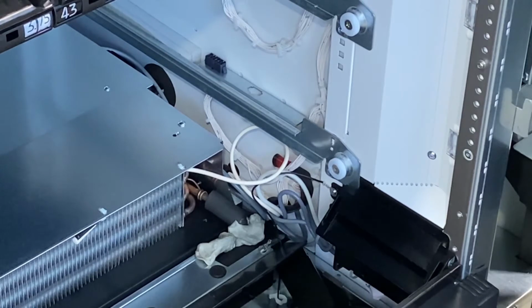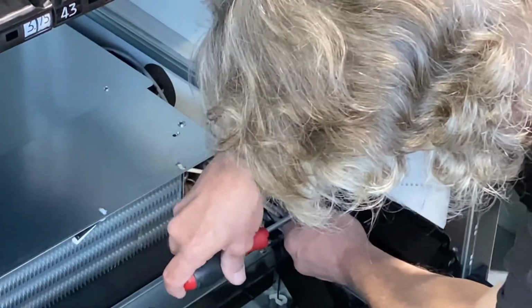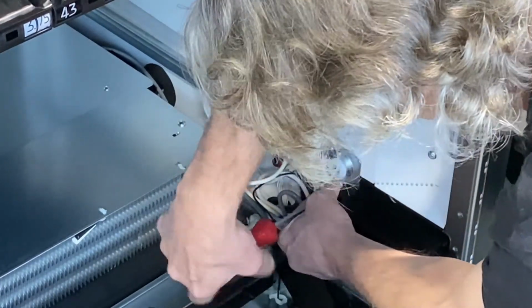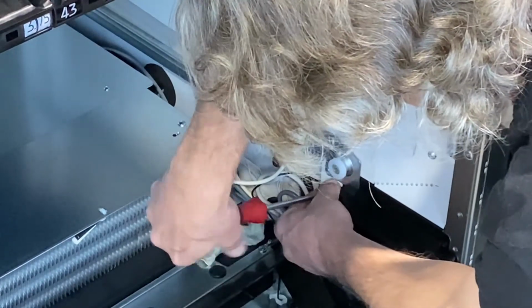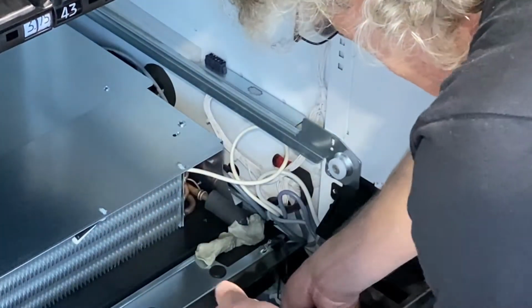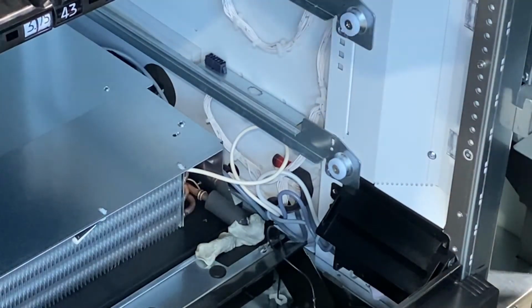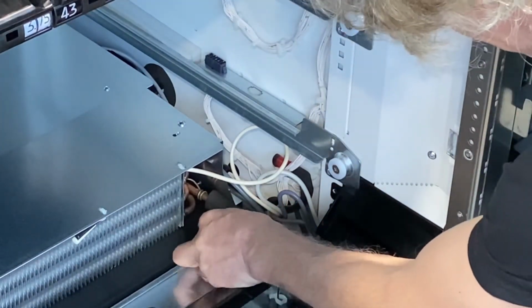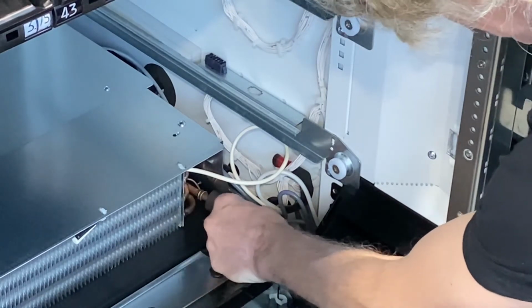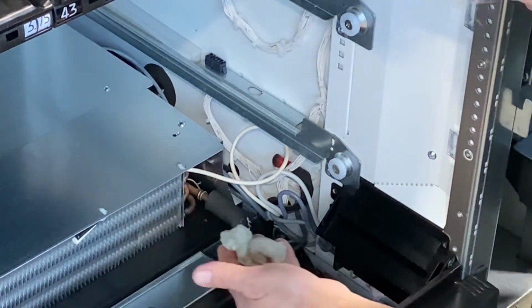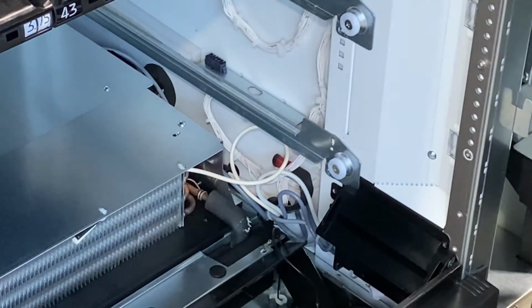The next step is to remove the earth wire and carefully remove the putty sealant between the delivery bin and the evaporator cell tray. The earth wire strap, tuck it neatly in, set aside the screw, carefully peel out the putty sealant. Keep it in good condition and keep it in a clean, safe spot.